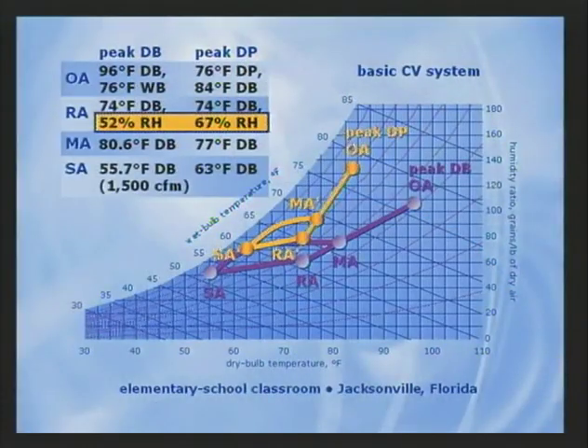Now, although this control action successfully maintains the desired temperature in the space, reducing cooling capacity in order to raise the supply air temperature makes the coil surface warmer. This results in less dehumidification and space humidity rises. At a part load condition, when the outdoor dry bulb temperature is not as warm, but outdoor humidity is higher, this basic constant volume system controls space temperature to set point, but space humidity rises. In our example, it rose to 67% compared to 52% at the full load condition. Again, reducing cooling capacity to raise supply air temperature at part load results in less dehumidification and elevated space humidity levels.